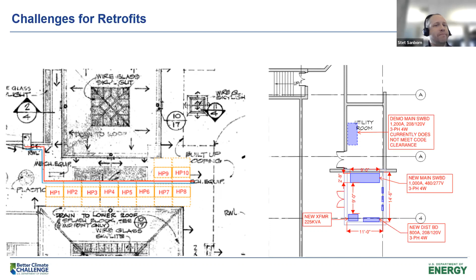One of the key things from an implementation standpoint that I want to highlight is that for those key hours in the morning, we were able to actually downsize the heat pump just by adding a thermal energy storage tank. We added around 2,000 gallons of storage for this project to get through those first three hours, in combination with changing the morning warm-up start point.